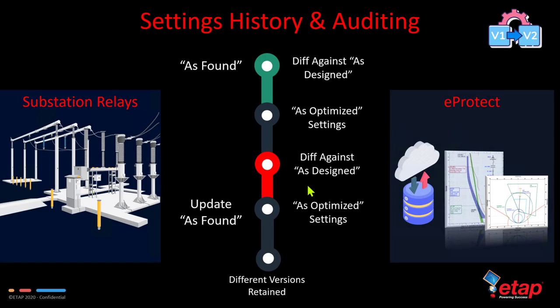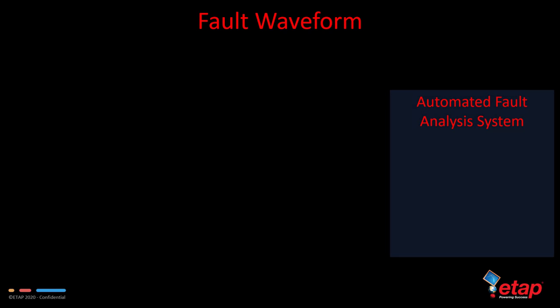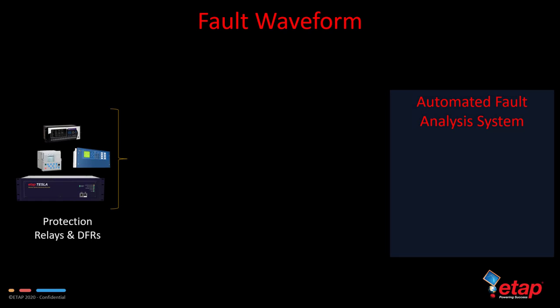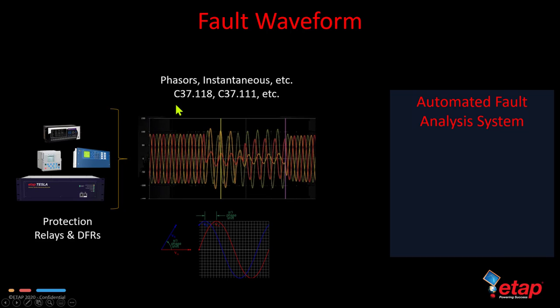Now that we've seen settings history and auditing in action, let's take a look at fault waveforms and how eProtect handles this type of information. Protection relays and DFRs not only send their individual settings and configurations, but they can also send waveform data such as phasor and instantaneous information using C37.118 or C37.111 and other formats. This information is sent to many different applications, including AFAS, which is Automated Fault Analysis System.